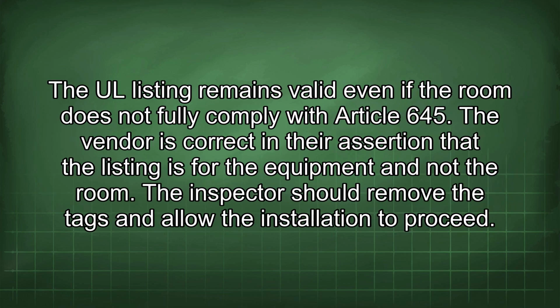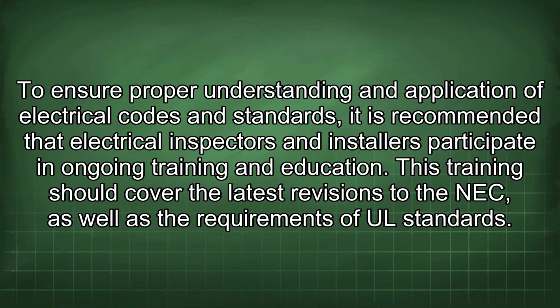The UL listing remains valid even if the room does not fully comply with Article 645. The vendor is correct in their assertion that the listing is for the equipment and not the room. The inspector should remove the tags and allow the installation to proceed. To ensure proper understanding and application of electrical codes and standards, it is recommended that electrical inspectors and installers participate in ongoing training and education.